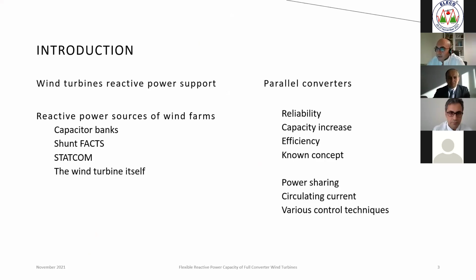As you know, wind turbines have a property of supplying reactive power according to the requirements of grid codes. It is one of the common points among all grid codes. When we look at the reactive power sources of wind farms, the initial source is the wind turbine itself. Other sources are capacitor banks, shunt FACTS devices, and STATCOMs.